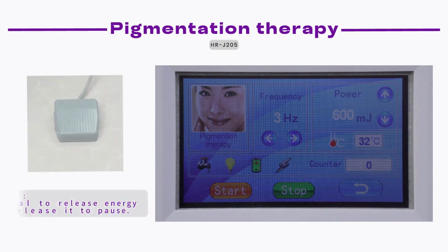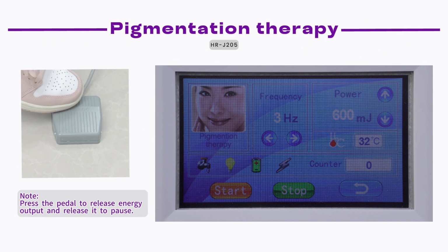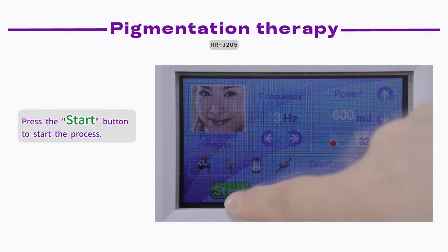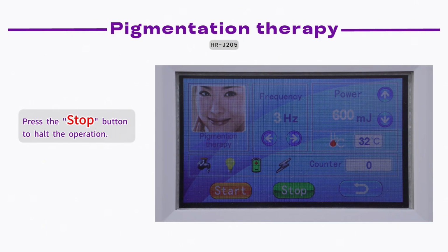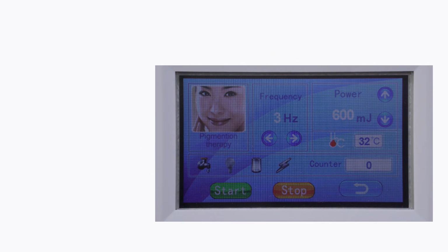Choose Pigmentation therapy. Settings. Frequency, 3 Hz. Power, 600 mJ. Note, press the pedal to release energy output and release it to pause. Press the start button to start the process. Press the stop button to halt the operation.